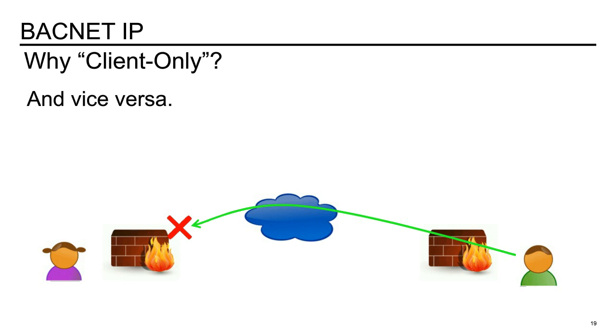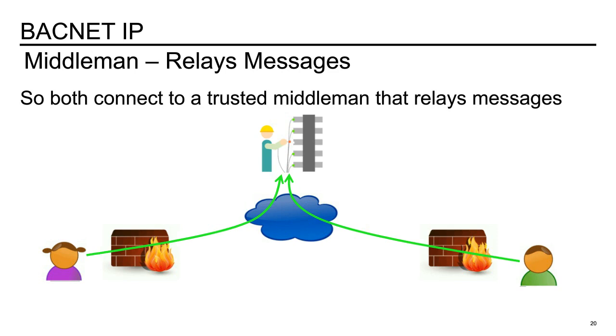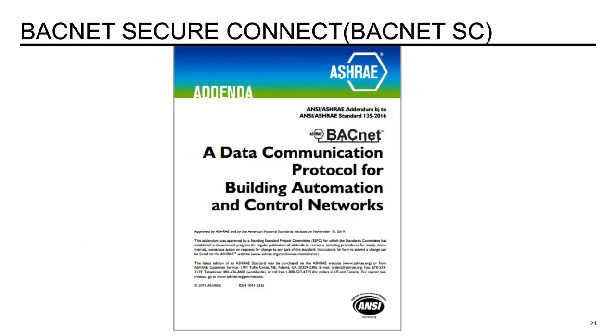So a way to solve this is to implement what's called a trusted middleman. And that's what brings us to BACnet SC or BACnet Secure Connect. BACnet Secure Connect was an addendum, it's addendum BJ, that was issued to ASHRAE Standard 135-2016 that was published in November of 2019.